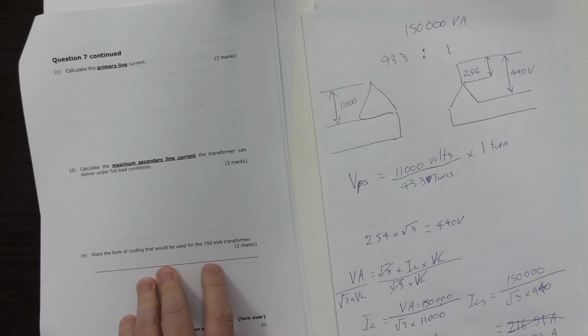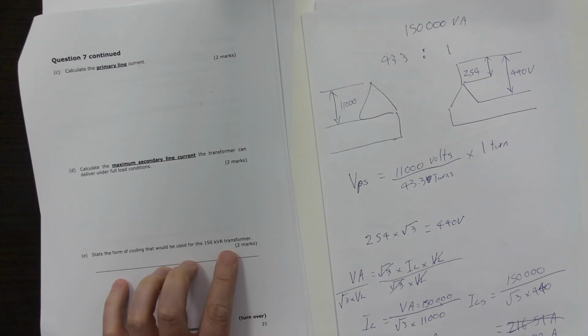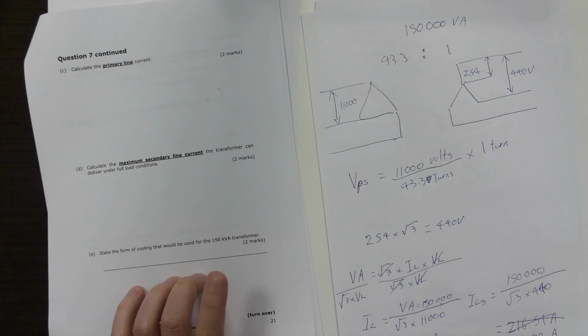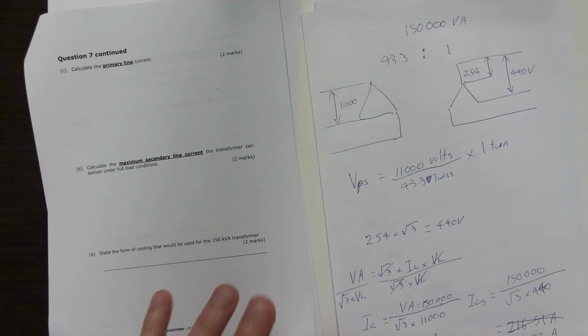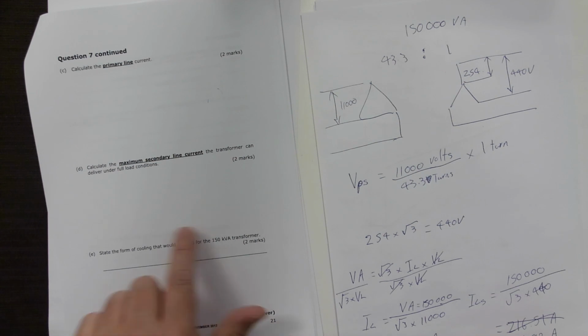State the form of cooling that will be used for the 150 kVA transformer. It'll probably be air cooled or oil cooled or forced air cooled. Take your pick, natural air convection, just pick one that is suitable for a transformer of that size.